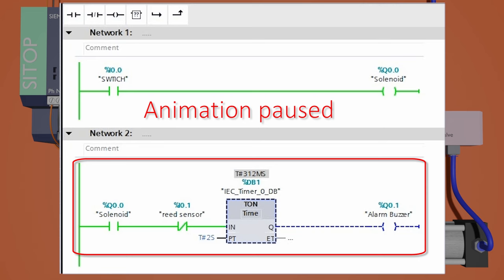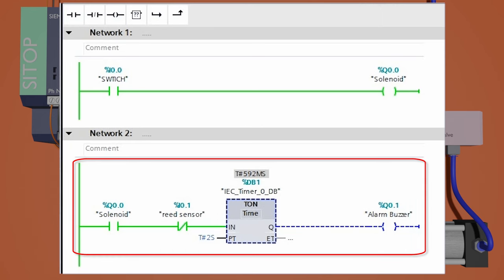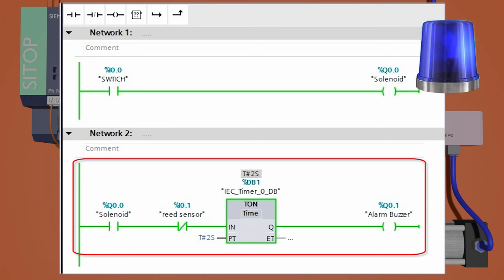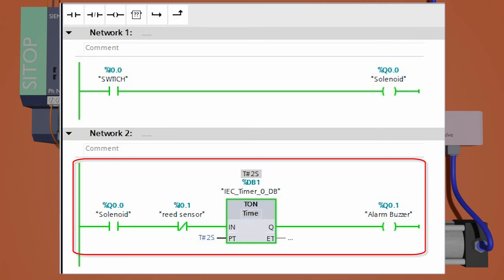The normally closed contact I0.1 will remain closed and it will activate the timer. If the cylinder fails to extend its shaft fully out in two seconds, it will activate the alarm buzzer in the machine to alert the machine operator to take corrective action.